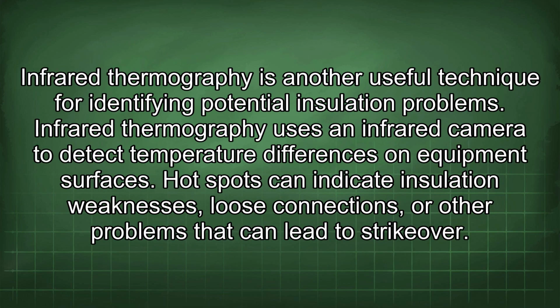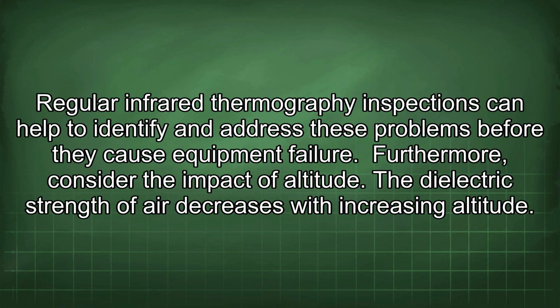Infrared thermography is another useful technique for identifying potential insulation problems. Infrared thermography uses an infrared camera to detect temperature differences on equipment surfaces. Hotspots can indicate insulation weaknesses, loose connections, or other problems that can lead to strikeover. Regular infrared thermography inspections can help to identify and address these problems before they cause equipment failure.